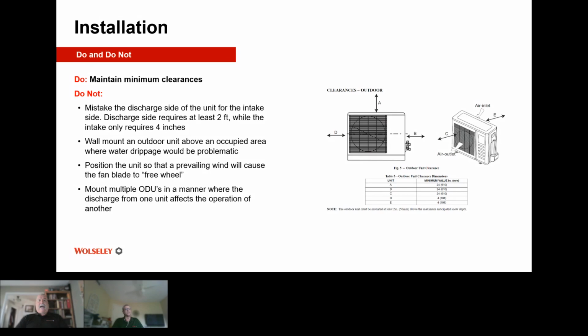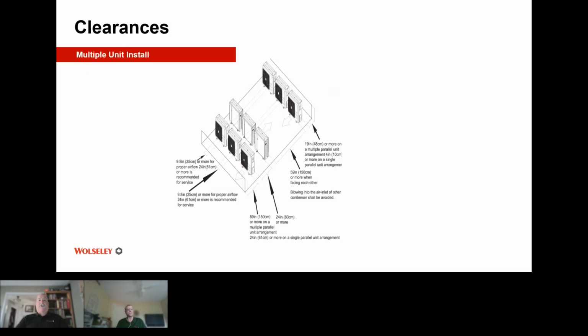We want to position the unit so that the prevailing wind will not cause the fan blades to freewheel. And then the final last one, don't position multiple outdoor units in a manner where the discharge from one unit will affect the other. So let's take a look at that. As you see in this picture here, if you are installing these in a multiple dwelling building, there are some considerations that we have to look at for clearances.